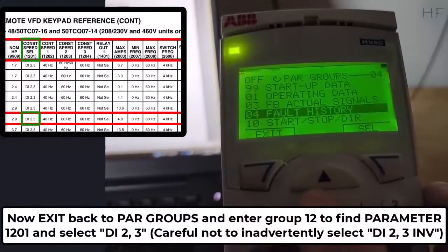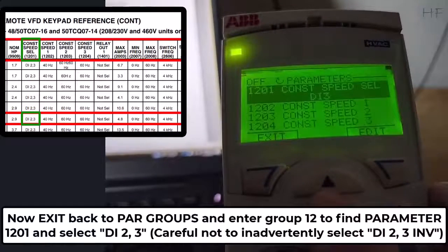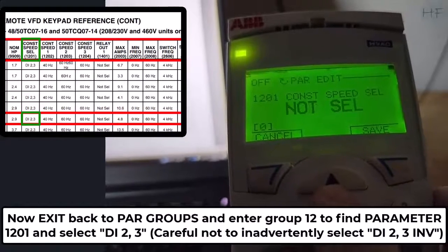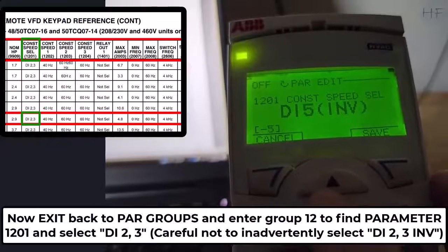Now exit back to parameter groups and enter group 12 to find parameter 1201 and select digital input 2 and 3. Be careful not to select the inverse option for this parameter.